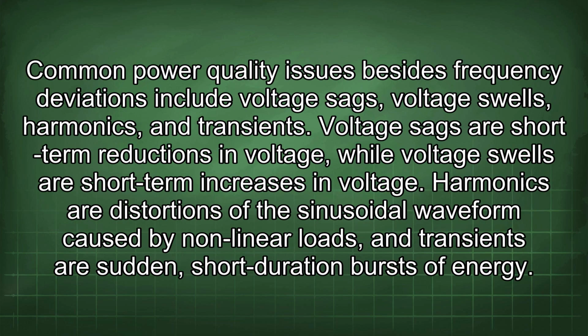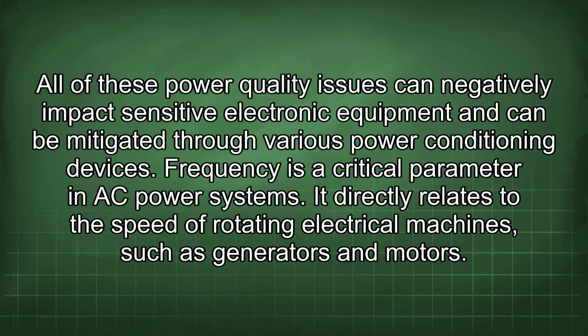Common power quality issues besides frequency deviations include voltage sags, voltage swells, harmonics, and transients. Voltage sags are short-term reductions in voltage, while voltage swells are short-term increases in voltage. Harmonics are distortions of the sinusoidal waveform caused by nonlinear loads, and transients are sudden, short-duration bursts of energy. All of these power quality issues can negatively impact sensitive electronic equipment and can be mitigated through various power conditioning devices. Frequency is a critical parameter in AC power systems.